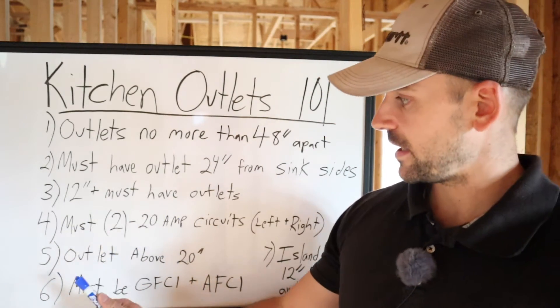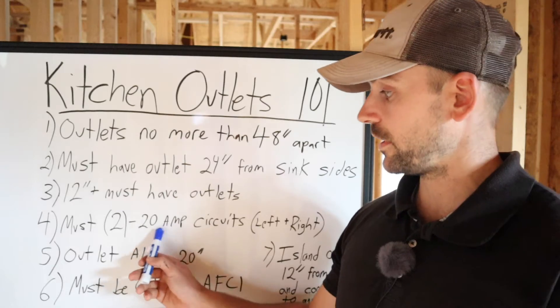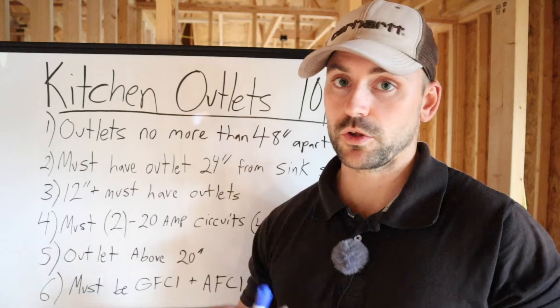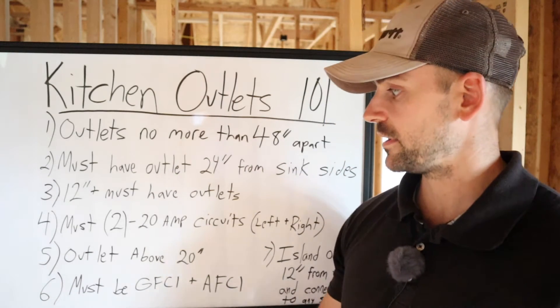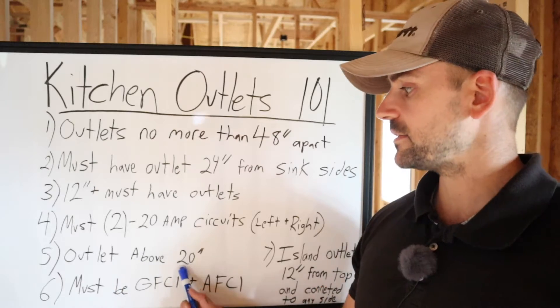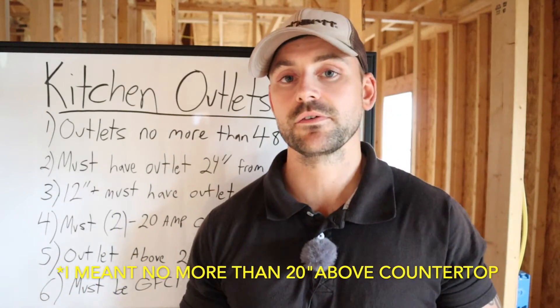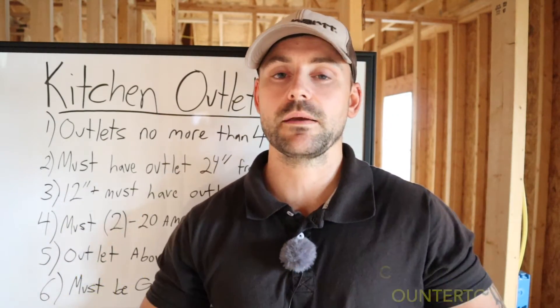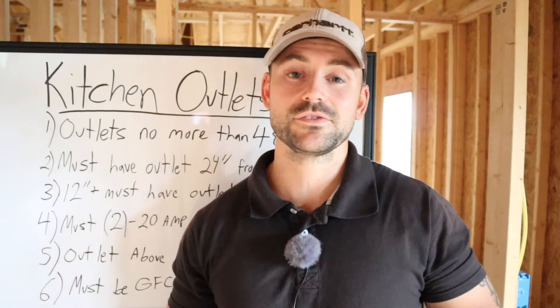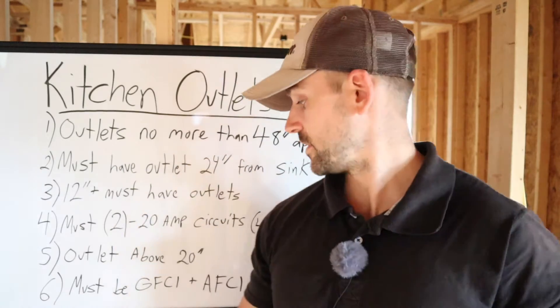When you run a 20-amp circuit, be sure to use 12-gauge wire — don't use any smaller gauge. Outlets must be no more than 20 inches above the countertop and can't exceed that height. That's fine because the typical height of upper cabinets is 18 inches, so you shouldn't be setting your upper cabinets any higher than that anyway.